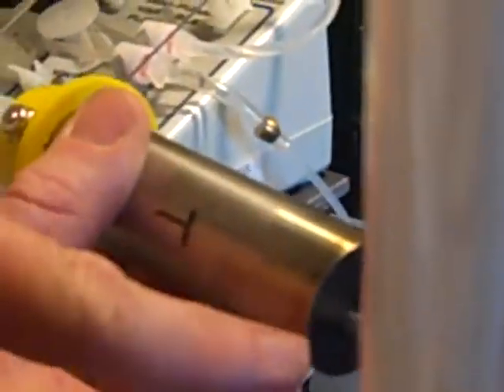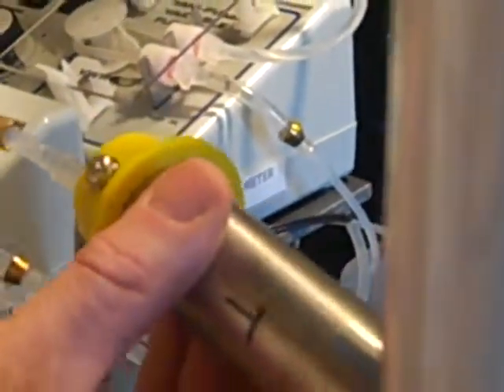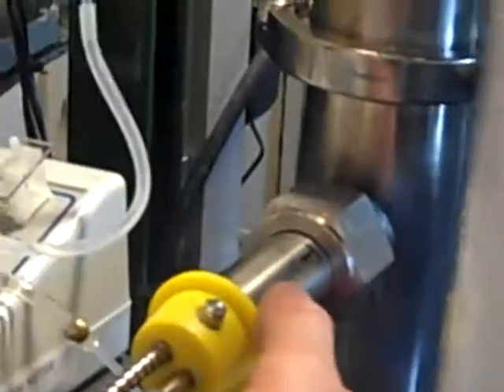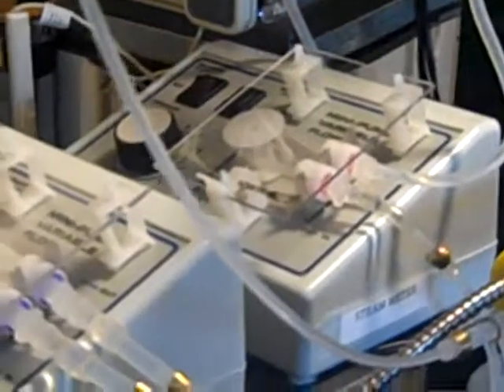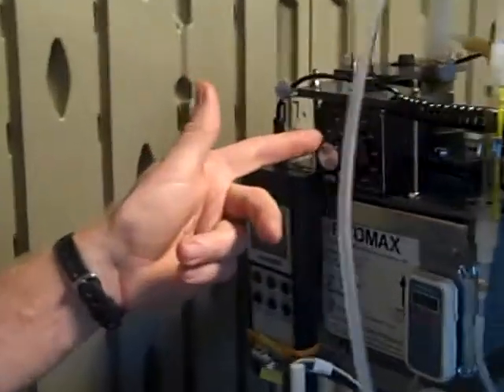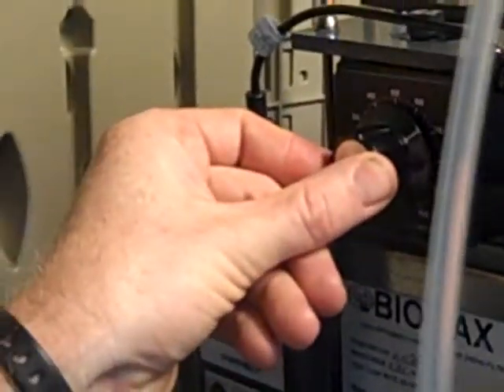Okay, once that's on, what we want to do is make sure that there's water coming out of the end of the steam generator. It's very low flow, so we can see that there is water dripping out. So if we don't have water running through the steam generator, it'll burn out. There's a mark on the steam generator showing how far it should go in. It should go into the perpendicular line. Now that we know that we have water going through, and we want to make sure there's not a lot of air bubbles letting air go through, we can turn the steam generator on with this control, and we want to set it at about 70.